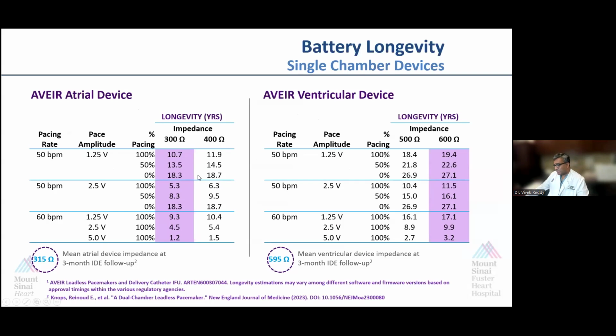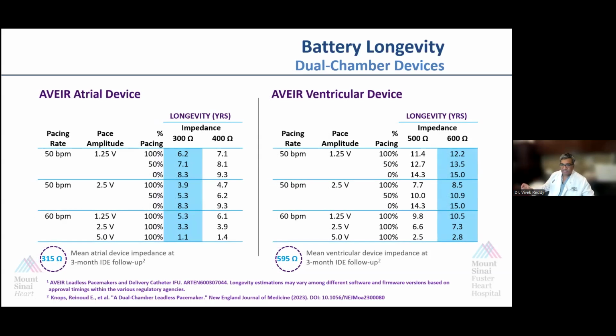Now, conversely, if it's pacing quite a bit, yes, the battery life comes down. And very importantly, those are single-chamber devices. When you combine the devices, and this is going to be a challenge that we have to deal with, when you have dual-chamber devices, if they're pacing infrequently, then yeah, you can get pretty good battery longevities, okay? By the way, if you have very high pacing amplitude requirements, then you can get extremely low battery longevity. Look at this, just 1 year, okay? So the implant pacing and sensing thresholds are very important. Fortunately, this is actually extremely rare, as we saw in the clinical trial.